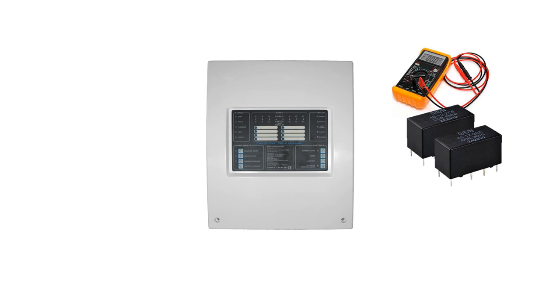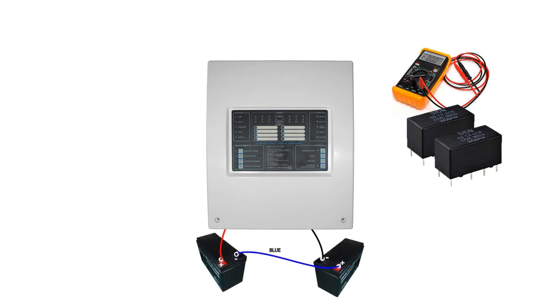To check the operation of the fault relay, disconnect the battery to cause the control panel to enter the fault condition. Check that the fault relay operates. Restore the battery connection and reset the control panel. Check that the fault relay resets.